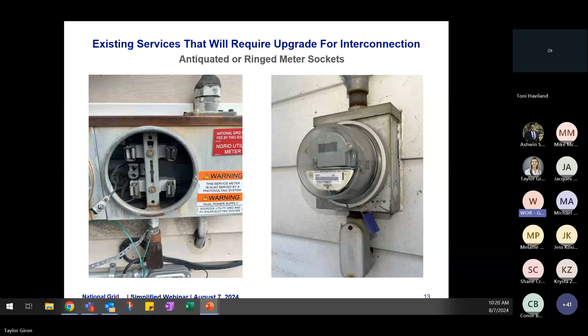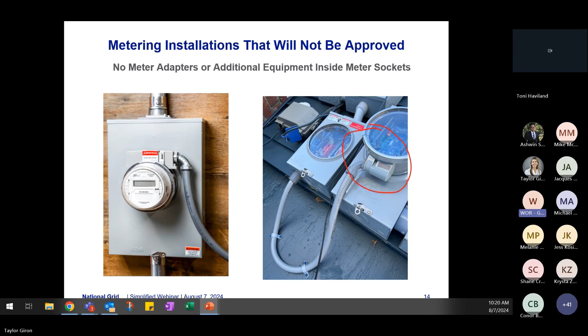National Grid, or any utility — Eversource, Unitil, anywhere in Massachusetts — none of us allow any kind of equipment in our meter sockets: no adapters, no additional equipment, anything. If you'd like to put this on your own customer-owned meter socket maintained by the developer or owner of the residence, that's perfectly fine as your disconnecting means. But if it's a utility-owned meter socket, a utility-owned smart meter, or a utility-owned net meter, these are not allowed and will not be approved — we will not be able to install a bidirectional meter for these types of installs. Next slide, please.